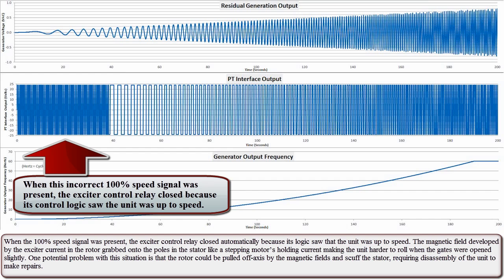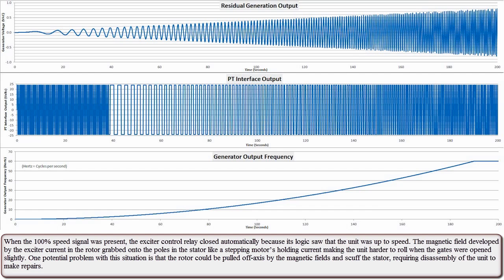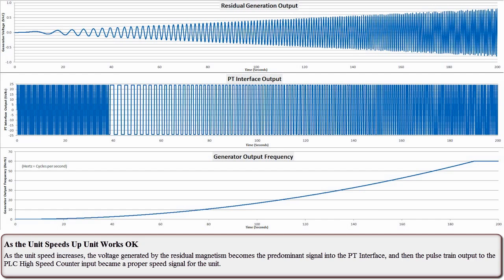When the 100% speed signal was present, the exciter control relay closed automatically because its logic saw that the unit was up to speed. The magnetic field developed by the exciter current in the rotor grabbed onto the poles in the stator like a stepping motor's holding current, making the unit harder to roll when the gates were open slightly. One potential problem with this situation is that the rotor could be pulled off axis by the magnetic fields and scuff the stator, requiring disassembly of the unit to make repairs. As the unit's speed increases, the voltage generated by the residual magnetism becomes the predominant signal into the PT interface, and then the pulse train output to the PLC high-speed counter input becomes a proper speed signal for the unit.